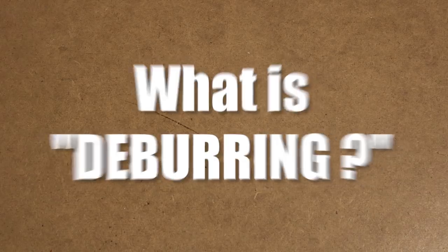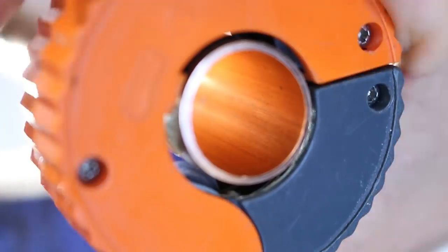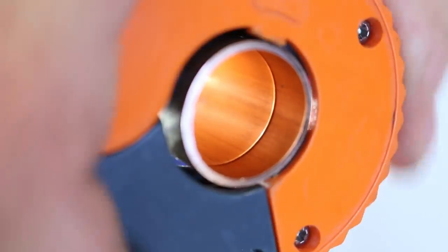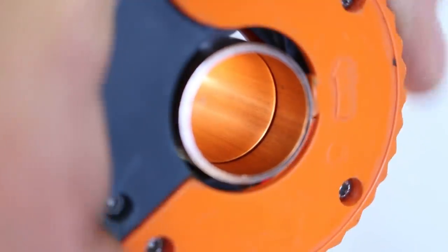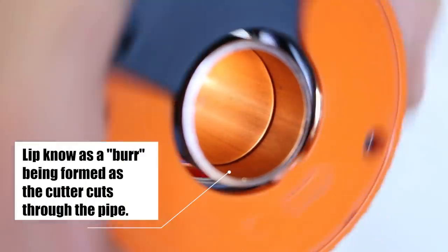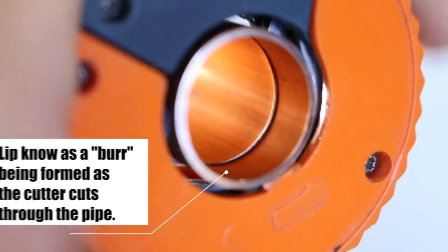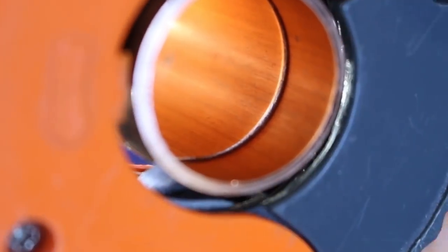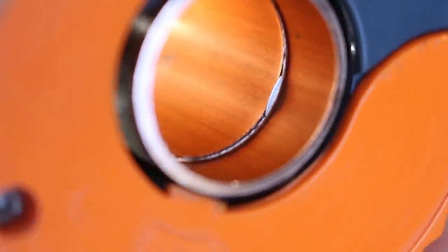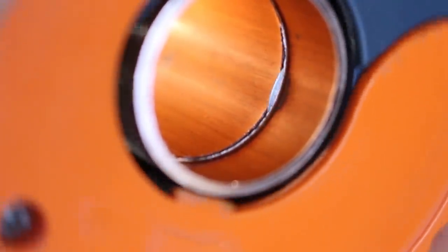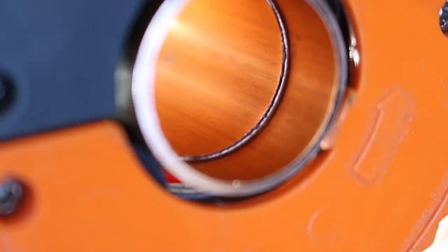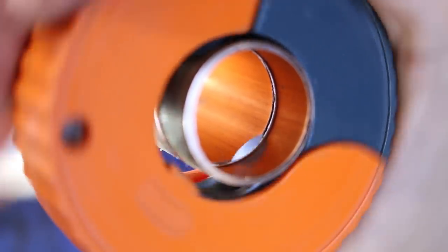So what exactly is deburring a pipe? Deburring is to remove the lip caused by a rotary cutter or handsaw after the cut using a deburring tool. When you cut a pipe with a rotary cutter like this one no material is removed. Instead it's displaced mostly inwards but also a little bit outwards leaving a lip or sharp edge on the outside and inside of the pipe.